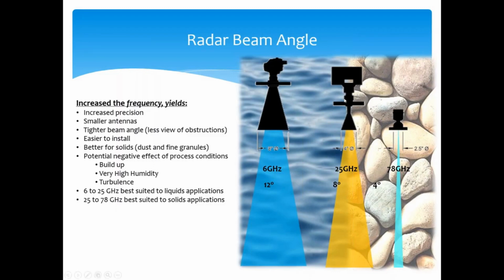So if we had a 12-degree beam angle and a 300-foot range, what's the problem? You're pretty much always going to be reflecting off the sidewall in an application like that. Those long silos might be 10 or 20 feet in diameter, and you're never going to make it down to the bottom. That's what these high frequency radars are used for.